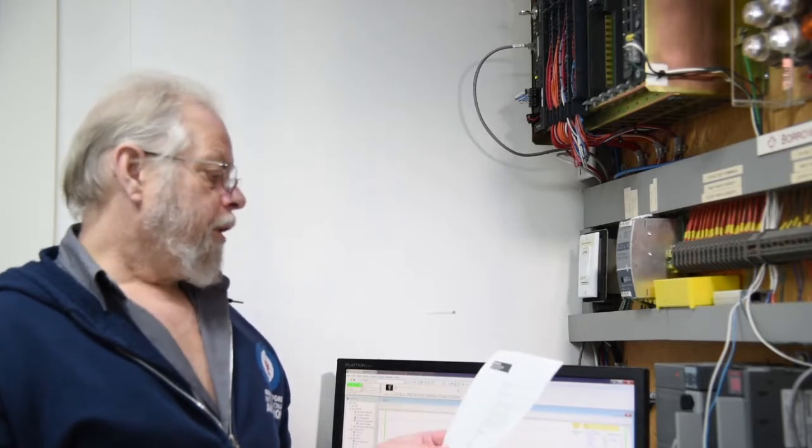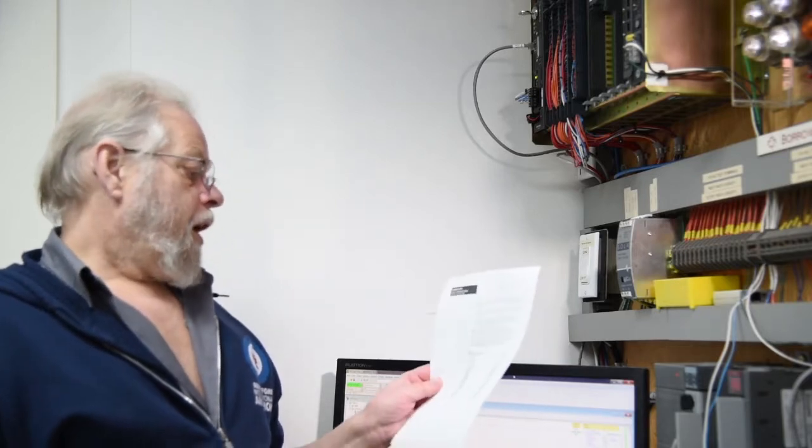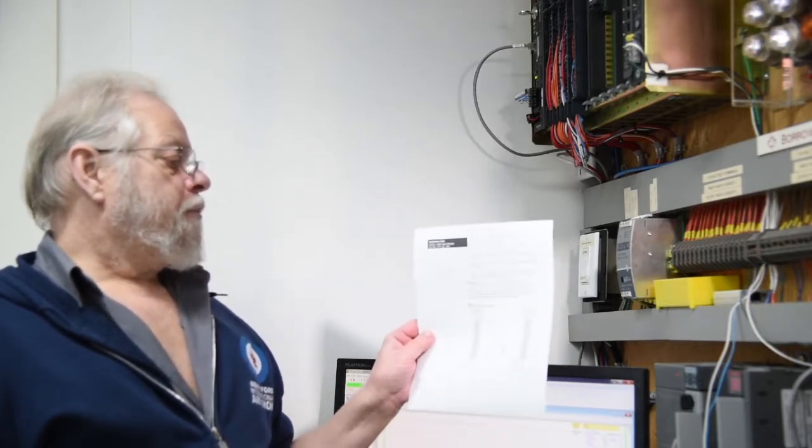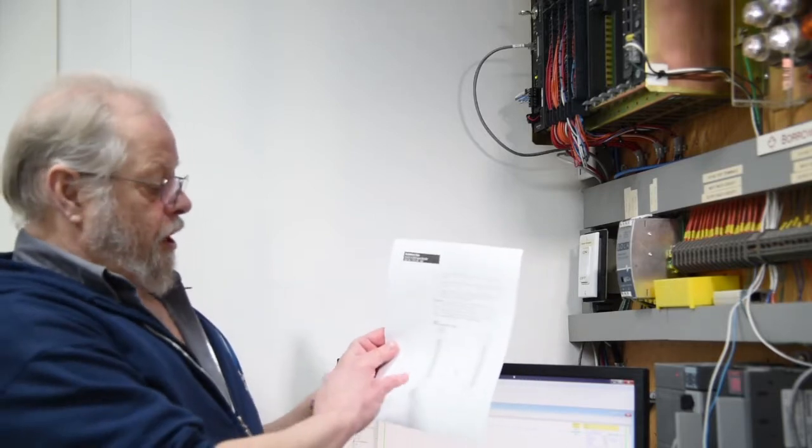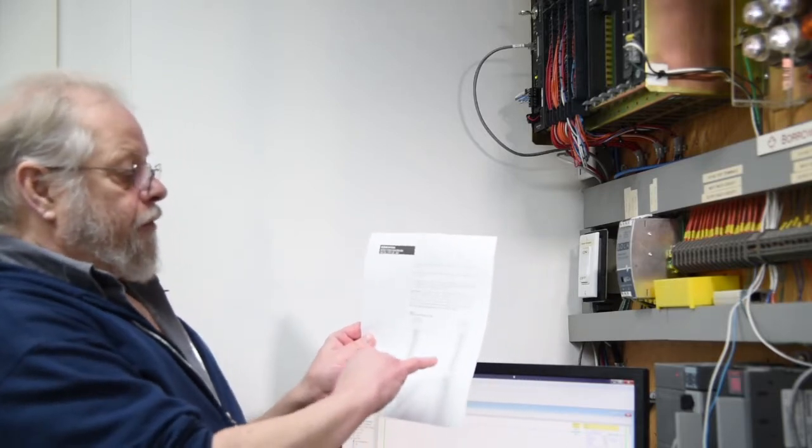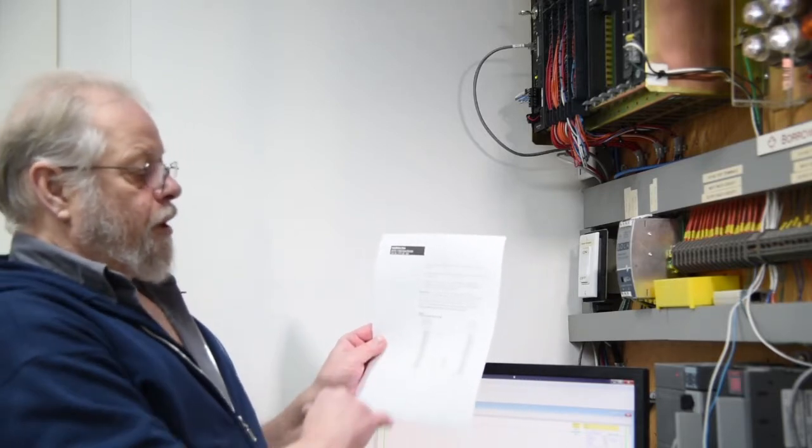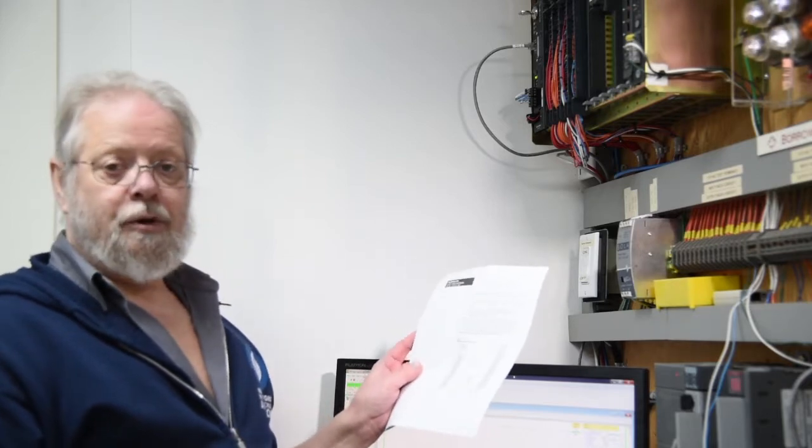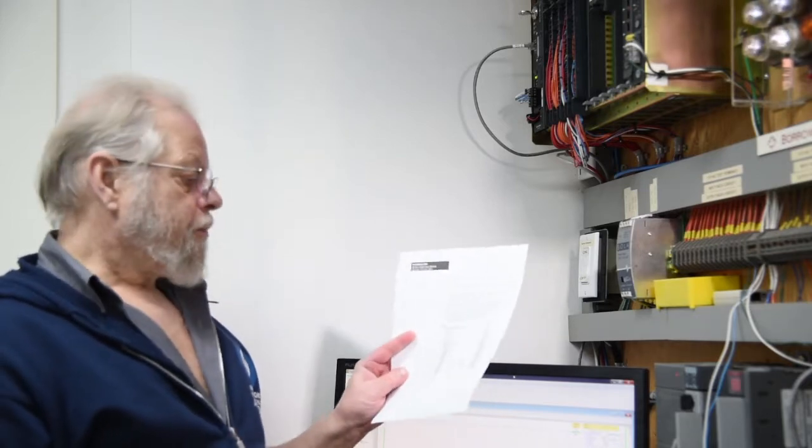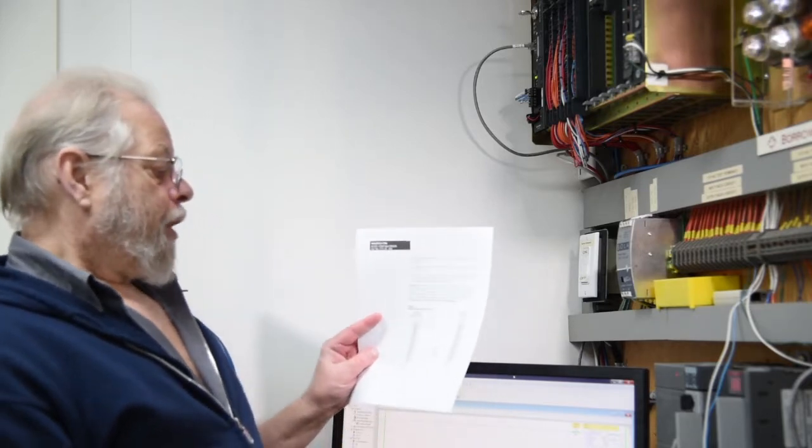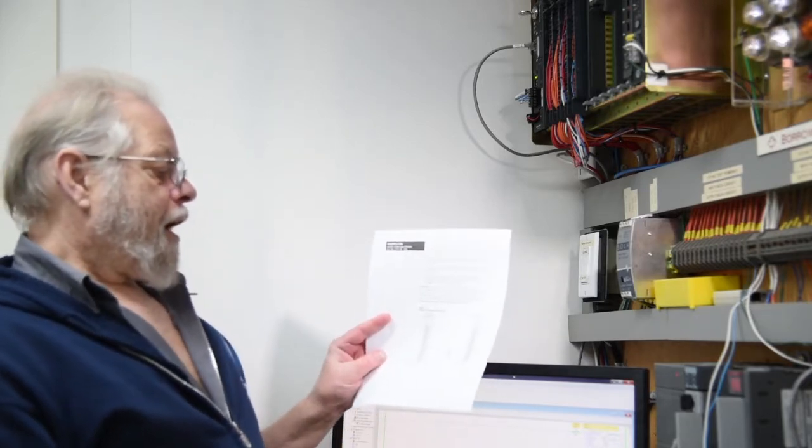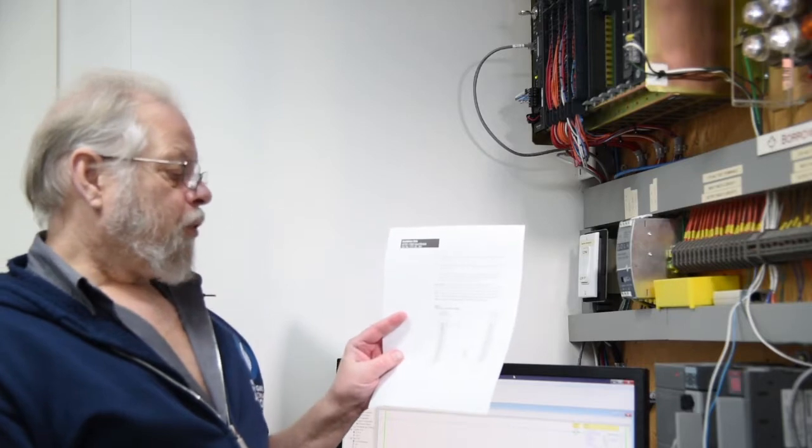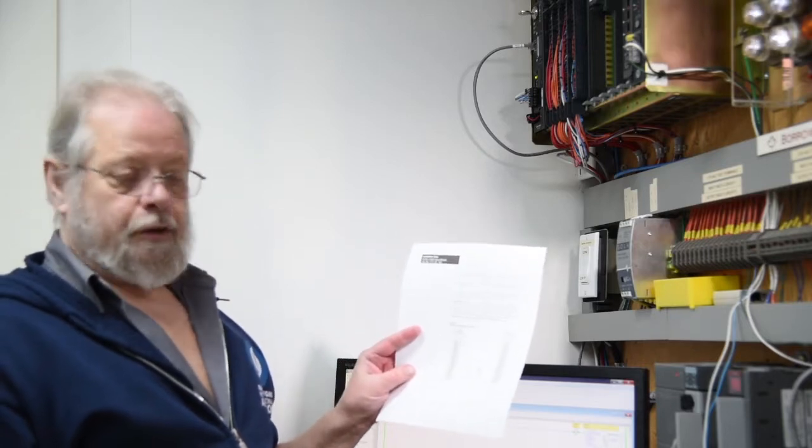Allen Bradley recognized this and put out a publication, and when you look at the publication, it shows you can drive an input with an output. No idea why you'd ever do that except for a testing situation like this. But you have to have a pull-down resistor.